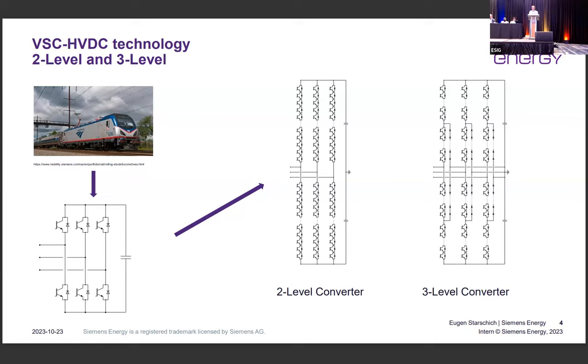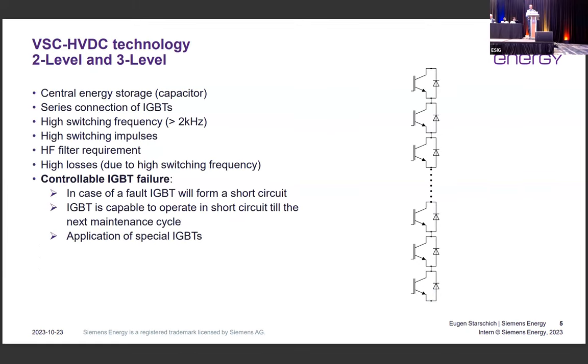And the biggest challenge in this setup was, if you have so many IGBTs connected in series and you have a failure in one of the IGBTs, you would like to avoid losing the full transmission power. So the key feature that was required at the time was, let's call it, a controllable IGBT failure. That means if one of these IGBTs fails, the converter still will be able to operate. That means the IGBT needs to form a short circuit when it fails.